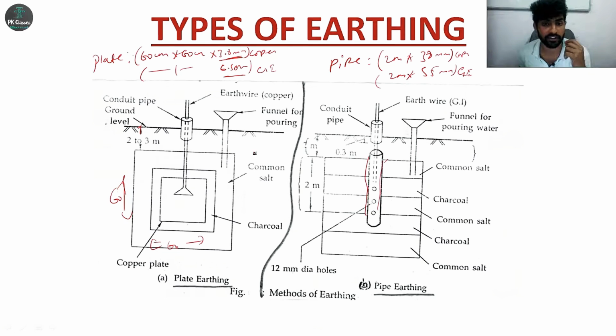electrode is different, right? So here plate electrode is placed vertically down into the earth, buried from the ground level 2 to 3 meter, right? And layer by layer charcoal and salt is placed, 10 centimeter, this is 15 centimeter approximately. So common salt and charcoal is placed to increase the conductivity of the soil and decrease the resistance of the soil. So salt is a good solvent, charcoal is a good absorbent, right?